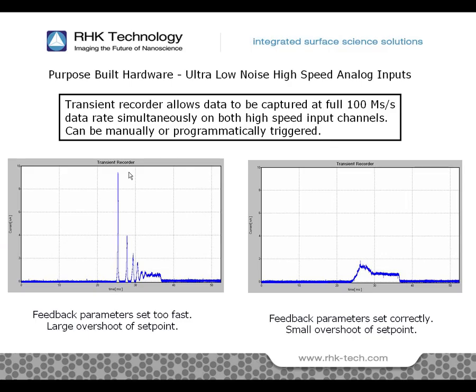In the example shown, the tunnel current is displayed in the last couple of milliseconds before and after the tip has approached the sample. In the first graph, you see the current spike a few times before the feedback loop has had a chance to regulate. Normally, this probably would result in a crash, and the only way that you would know it is if you saw a hole in the middle of your sample.